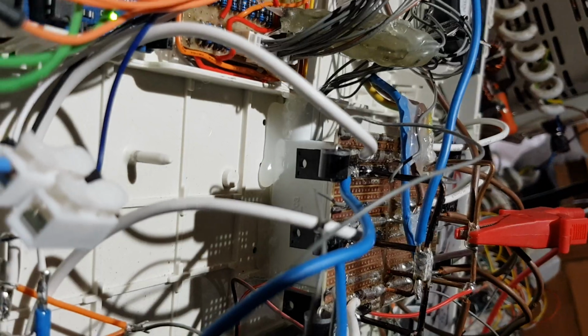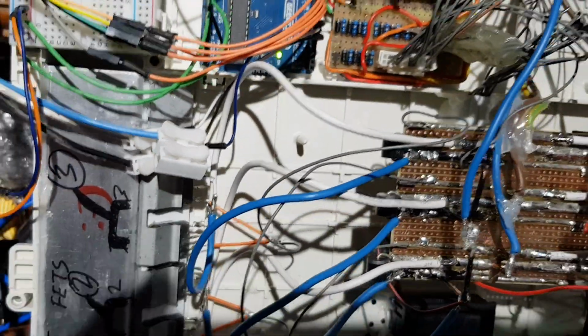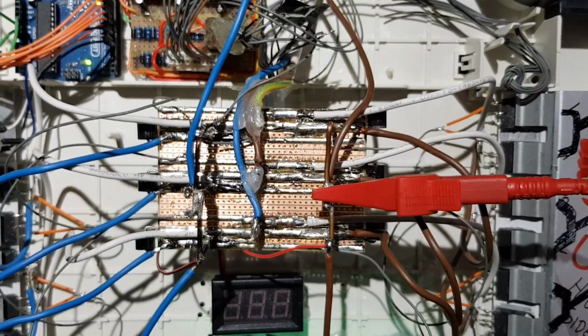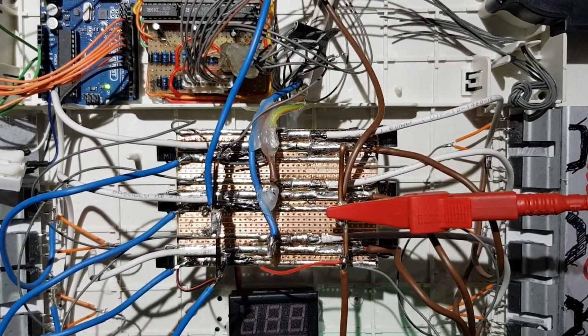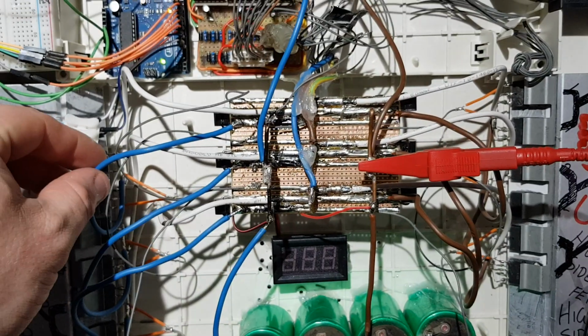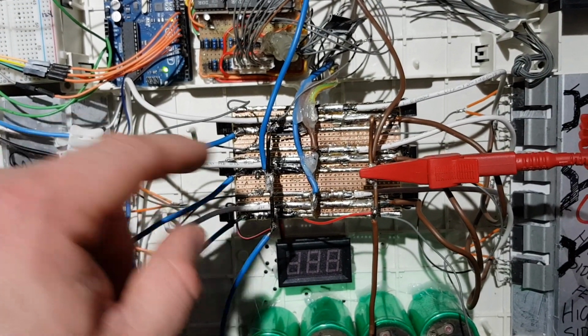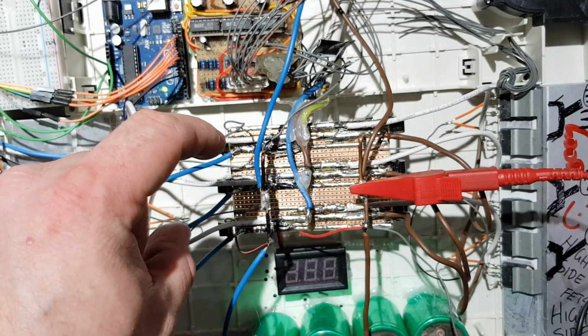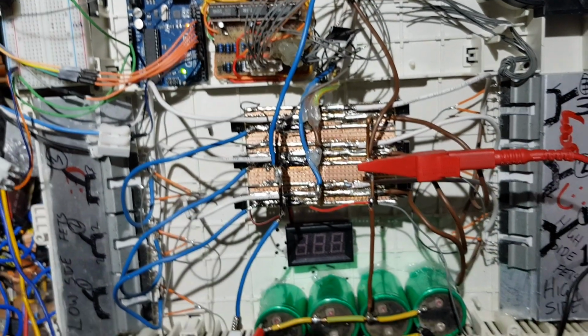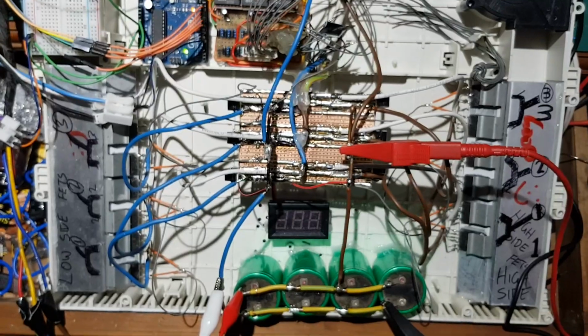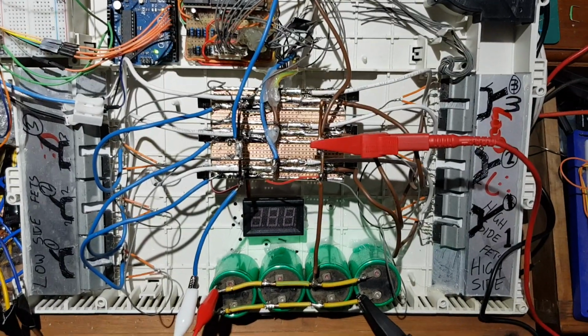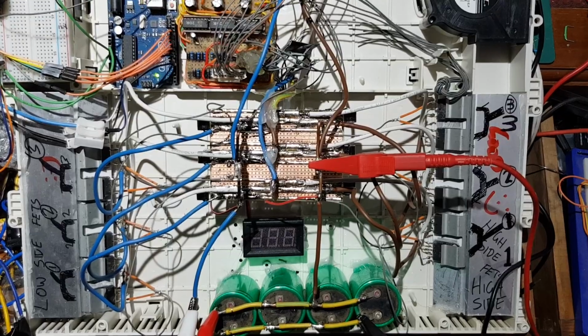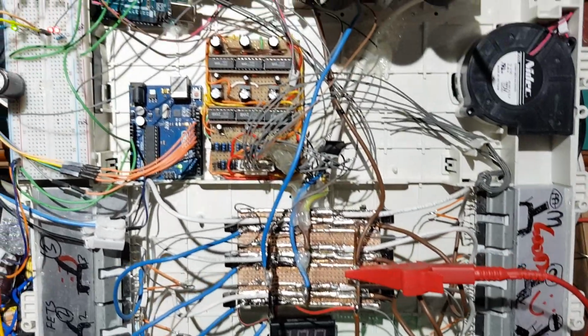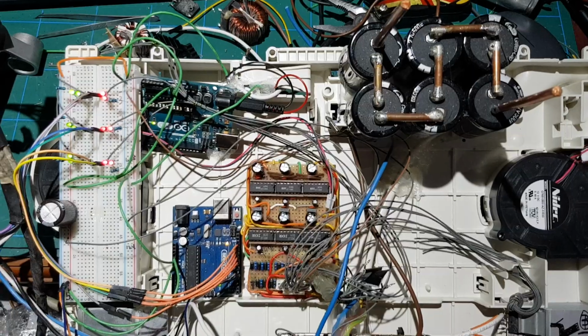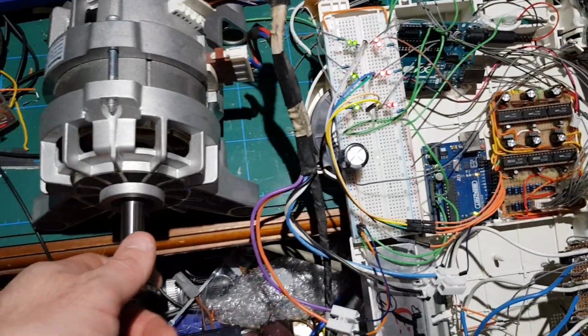Do you remember last time we had the full bridge rectifier for single phase? Well, this is essentially a full bridge rectifier for three phase. It has six diodes instead of four. So all that energy that's captured from the back EMF is again rectified and fed back onto the DC bus, which gives you really good regen braking and a very efficient inverter. It's what most inverters have. It's nothing special, but you need to have the right stuff. Otherwise, you don't want to be going out there with an...